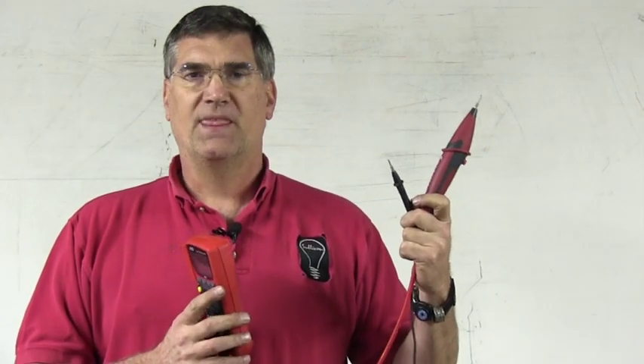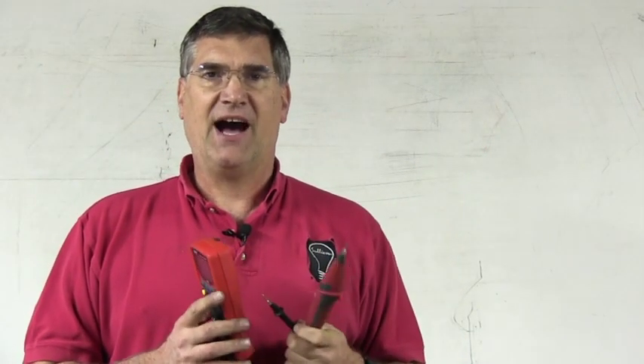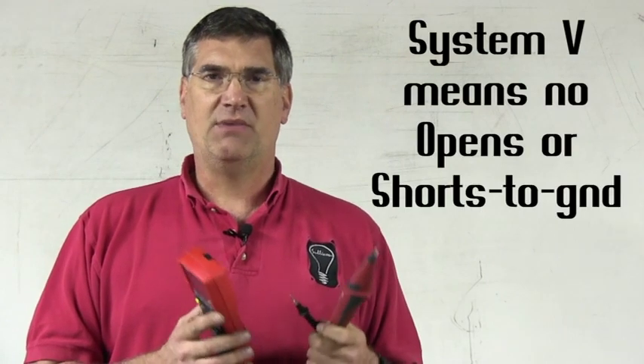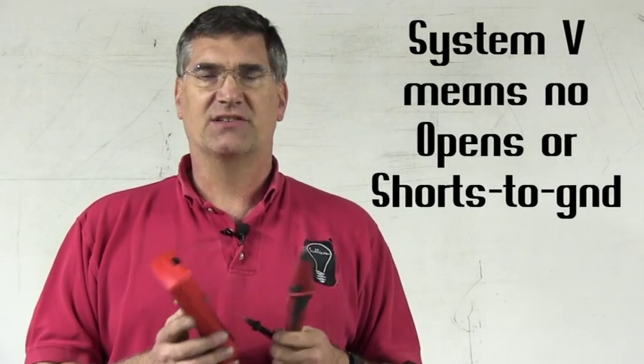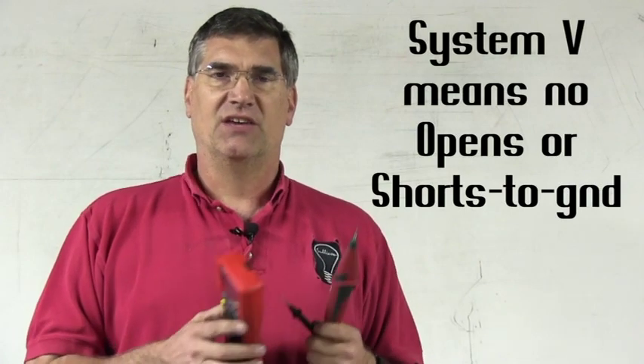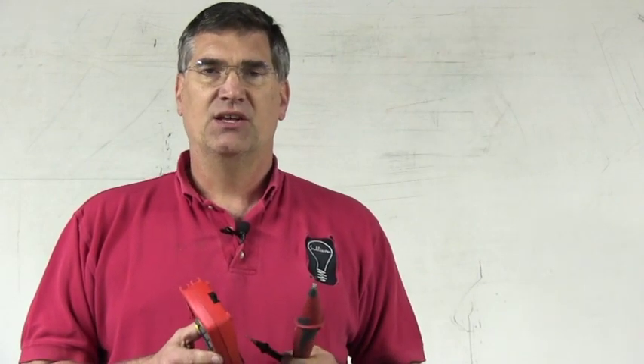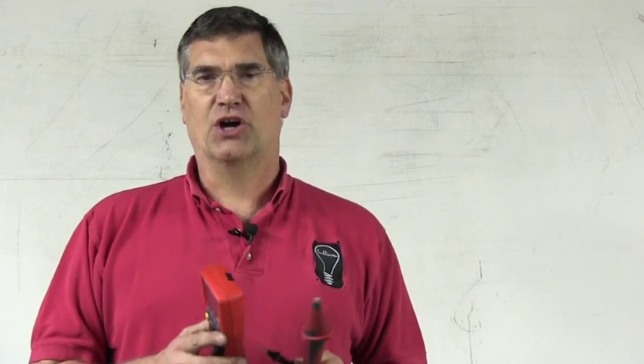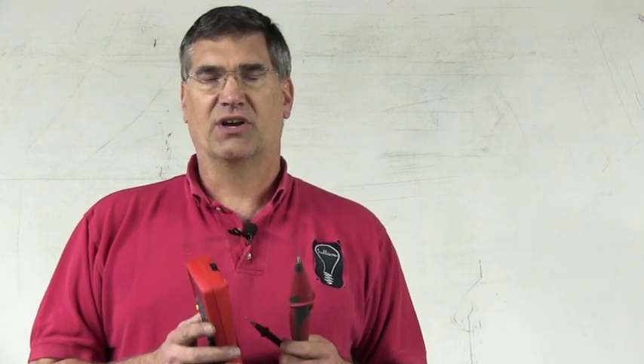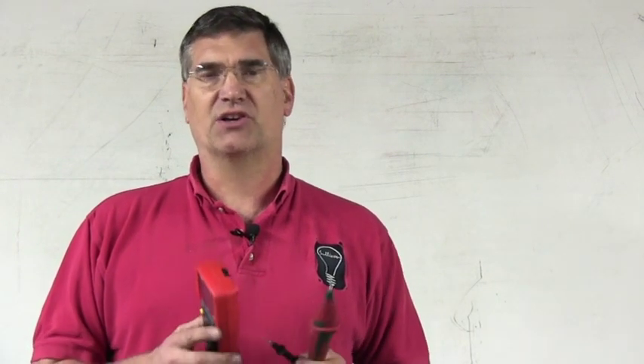When you use the 485 with the Load Pro voltmeter leads, this gives you the opportunity to find the third fault, which is high resistance. All you would do is simply read voltage as you normally would. If you see system voltage, it means you do not have an open or short. That's what it means. Open circuit cannot allow you to see voltage. If you have an open, you won't see voltage. If you have a short to ground, you won't see voltage. So when you see system voltage, it means you have no opens and no shorts in the circuit, as long as you're testing at the end of the circuit with the load component removed and the circuit turned on.